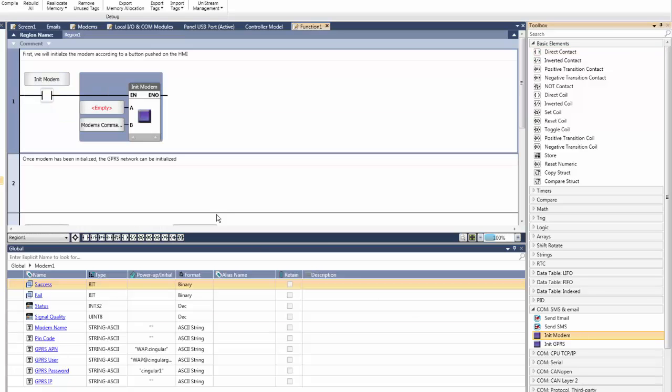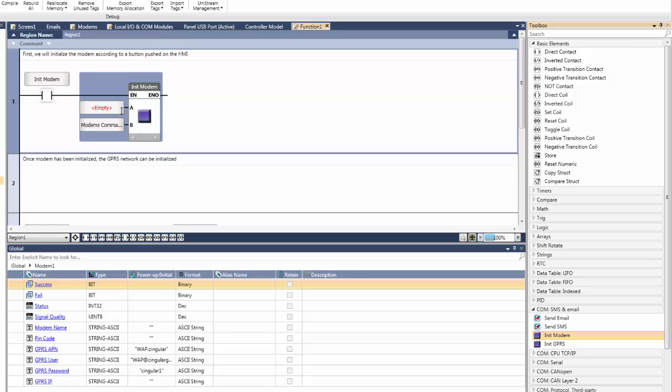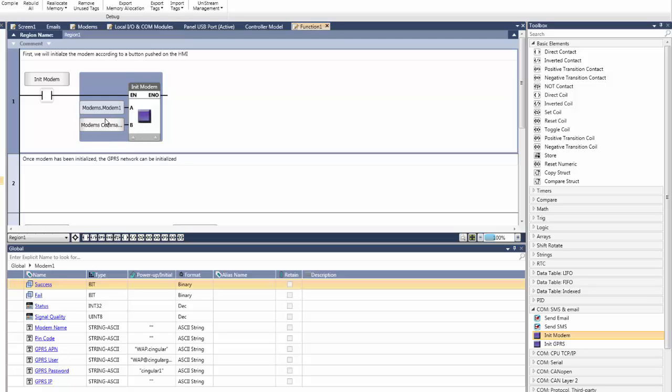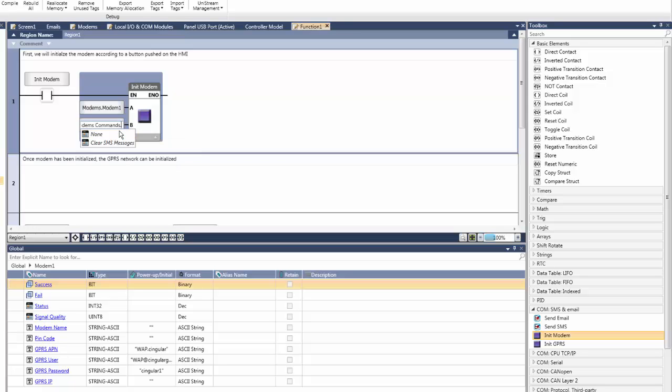Hover over the A parameter for this function block. See the input is looking for a modem with which we would like to initialize. For this project, we will choose modem 1, which we created earlier. The B parameter is looking for any additional tasks to perform upon initialization, such as clearing the SMS messages. We will leave this as none for this example. Next, finish the rung by resetting the initialized modem bit.